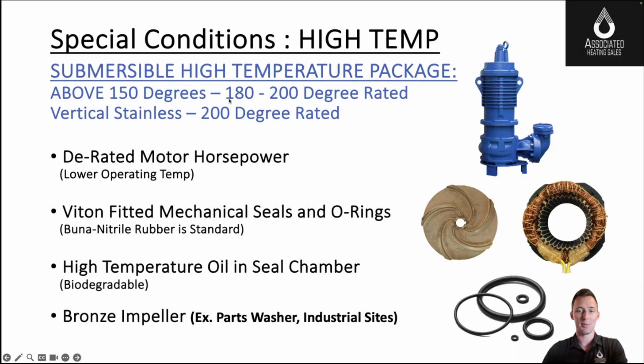Let's say you're below 180 and you want a submersible pump system. Weil in their high temperature pump package will put a derated motor that operates at a lower temperature, Viton seals instead of nitrile that hold up well, high temperature oil in that seal chamber, and you'll have a high temperature pump in the submersible category. Oftentimes a bronze impeller too. If you are close to boiling at 200 degrees and you have an indoor pit where it's shallower, you don't have a deep basin, a vertical system, like we mentioned before, it could work really well. So some different options here.